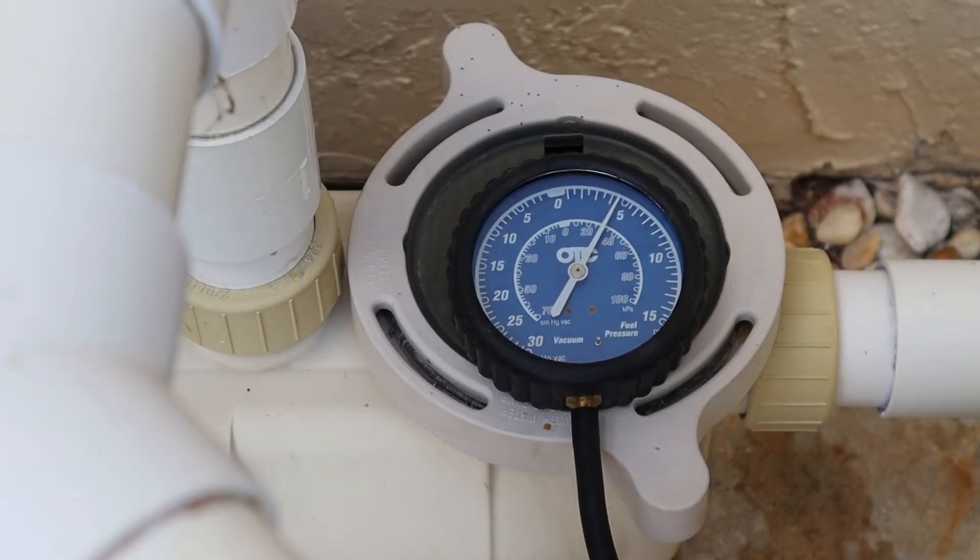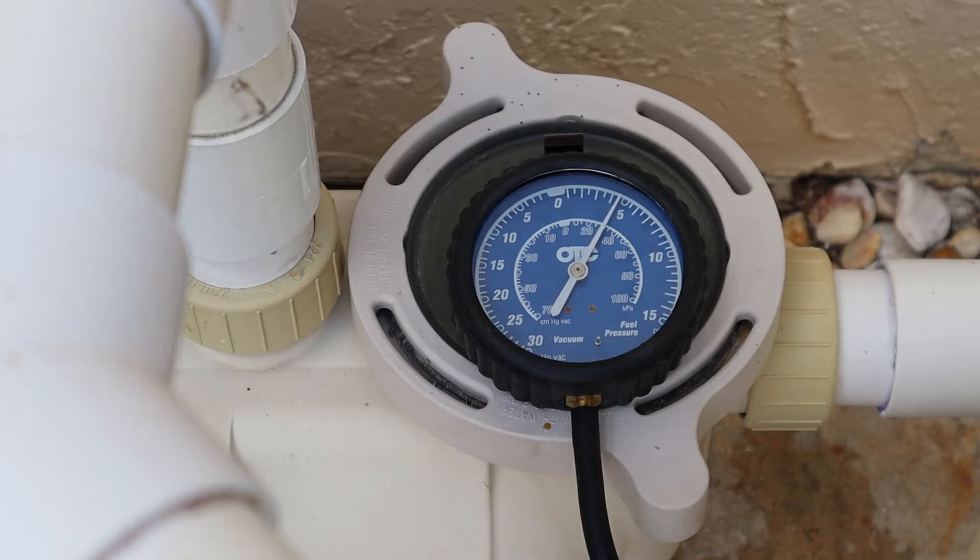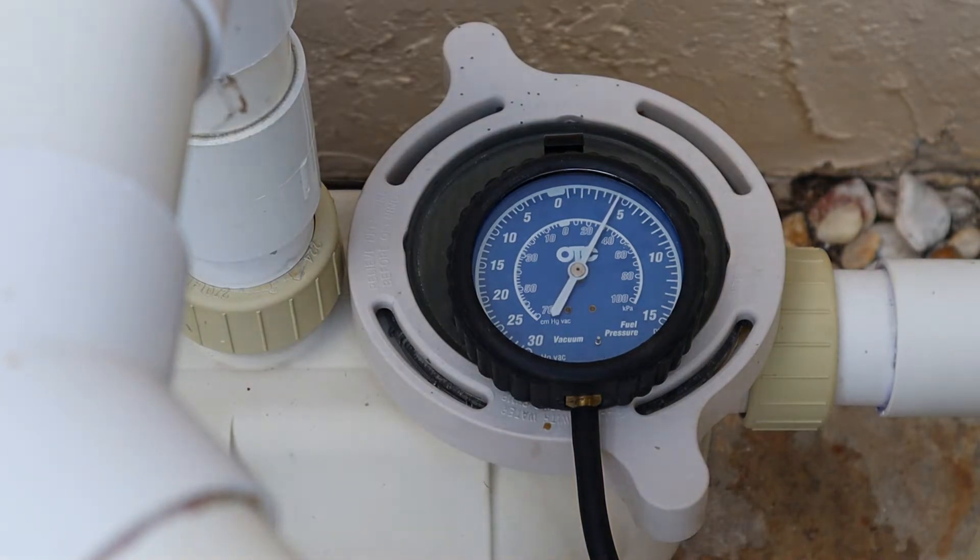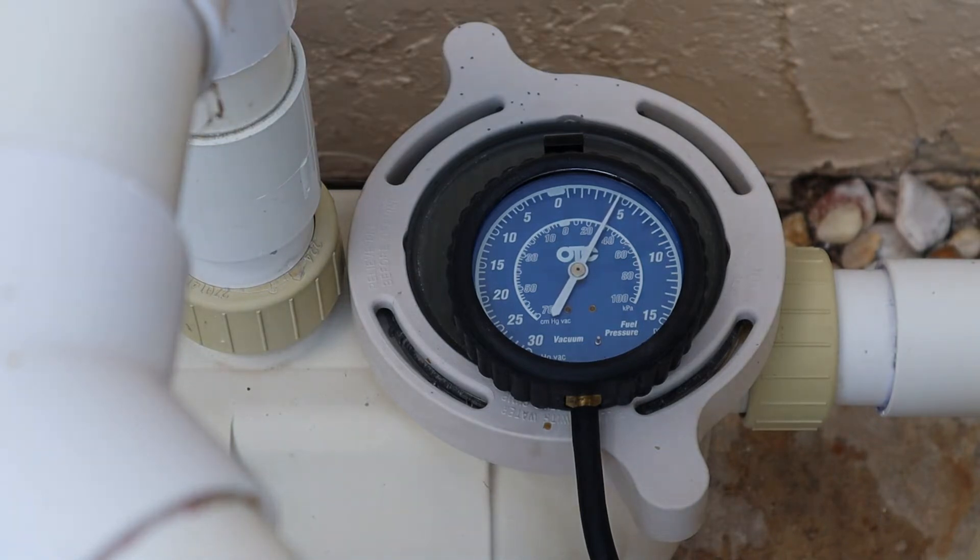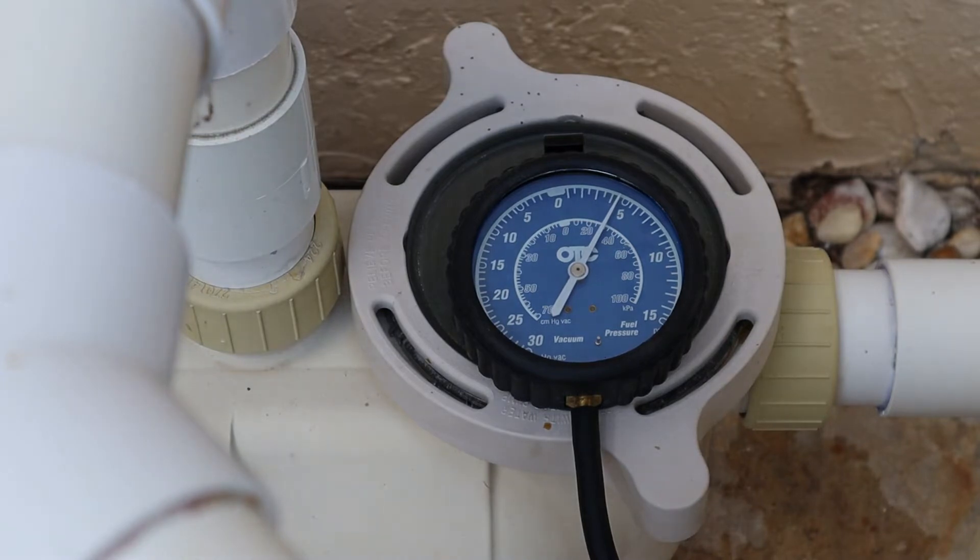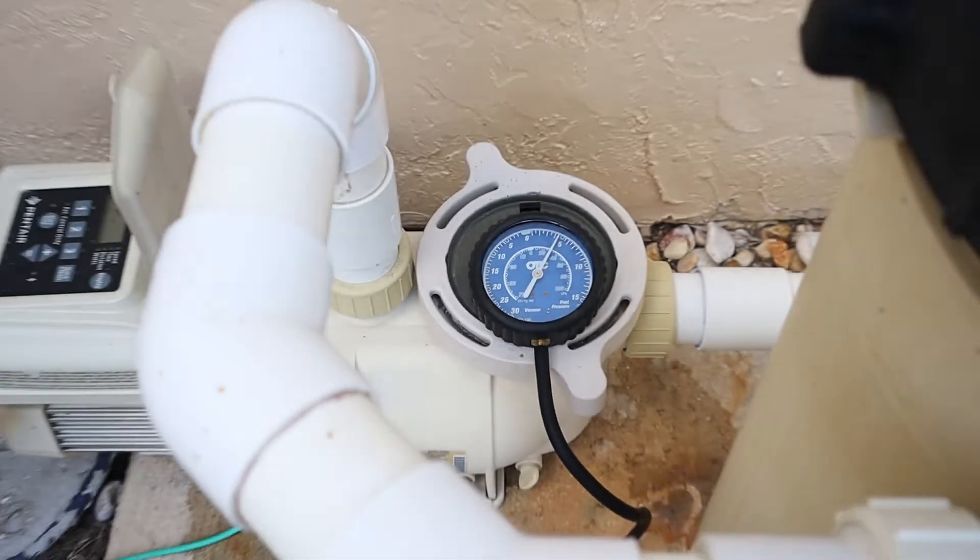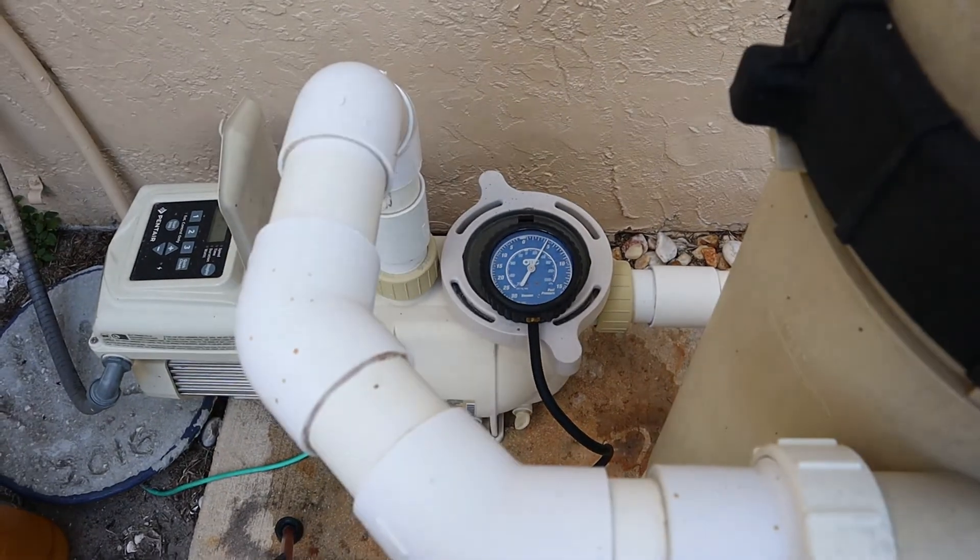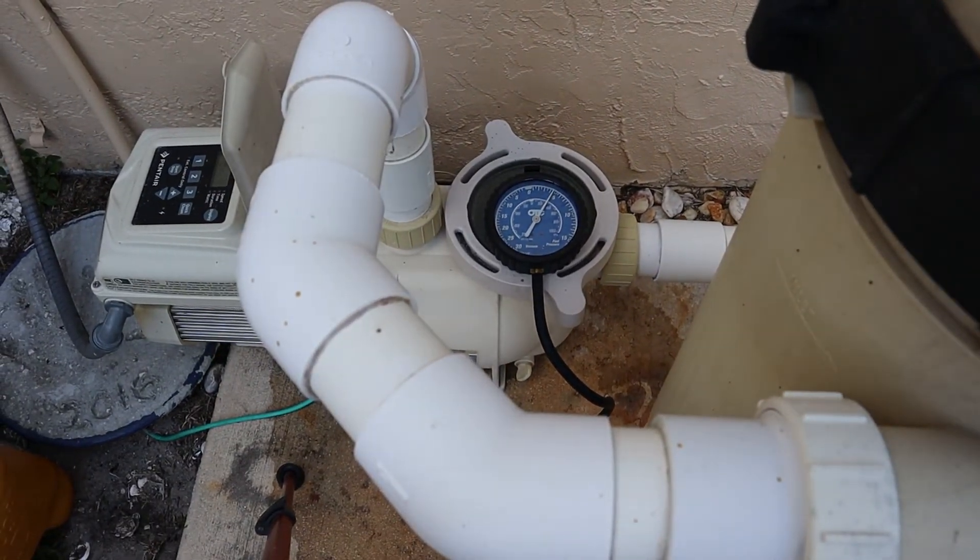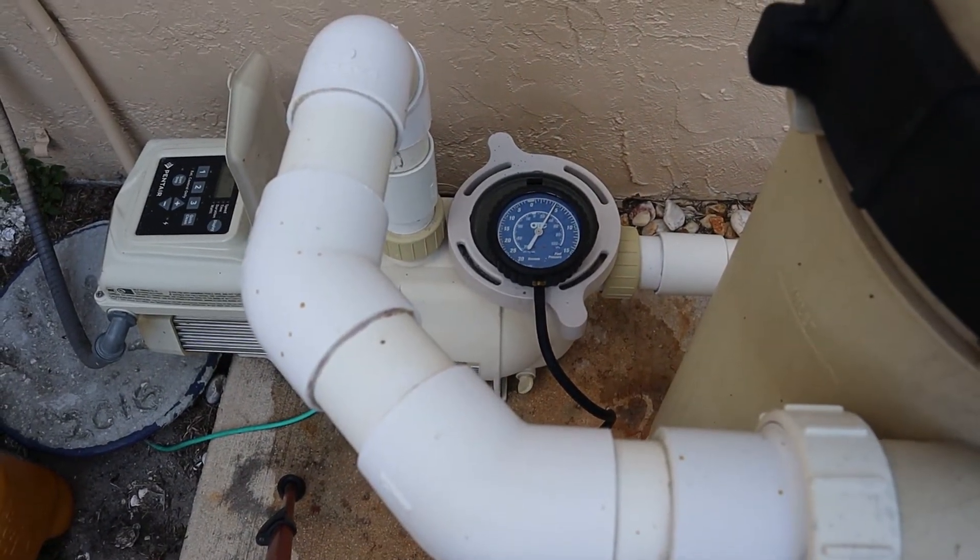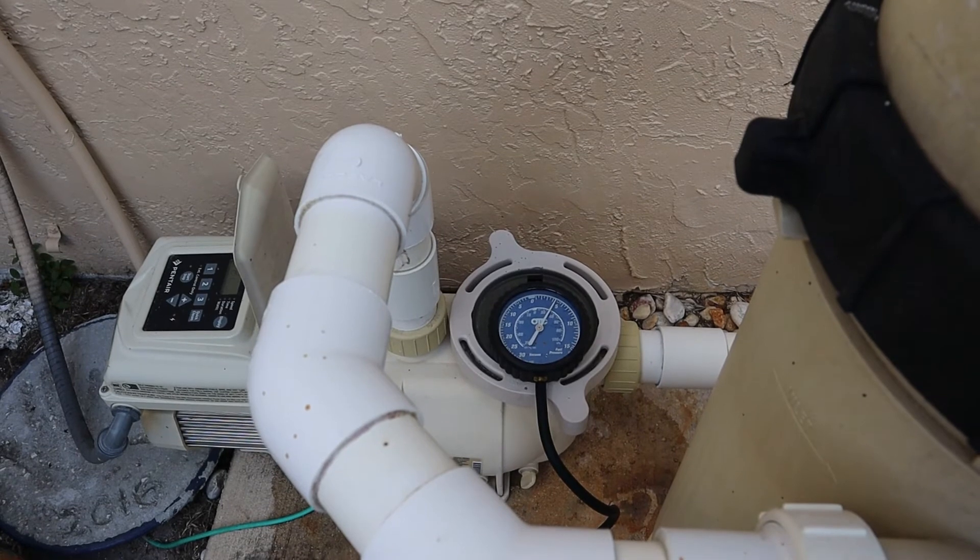Actually guys, I stand corrected. My apologies. I moved the pressure/vacuum gauge over to the pressure port and notice the reading is just below 5 PSI, about 4 PSI. But my filter only reads 2. So either my filter gauge is bad or the friction in this section of pipe is not negligible like I thought.